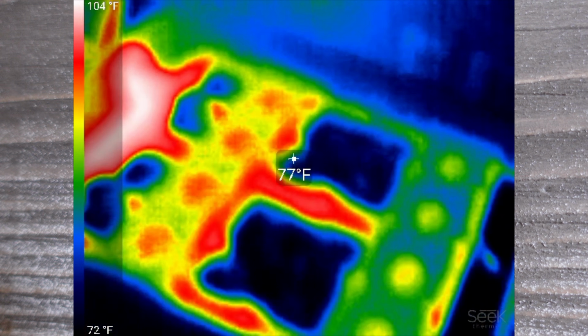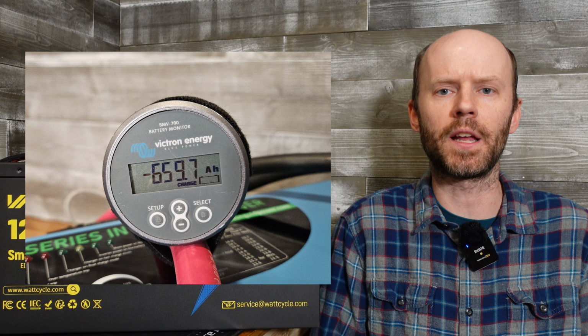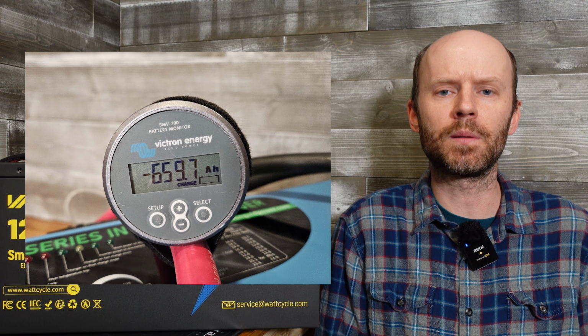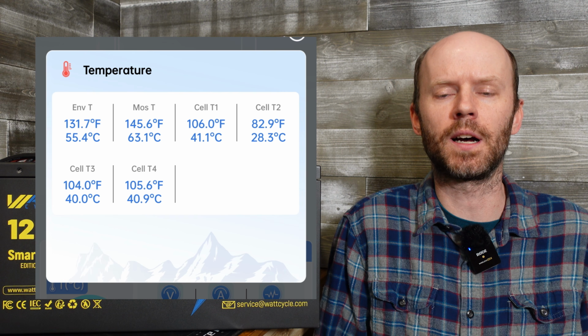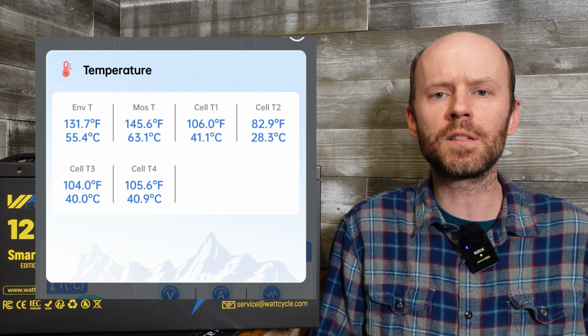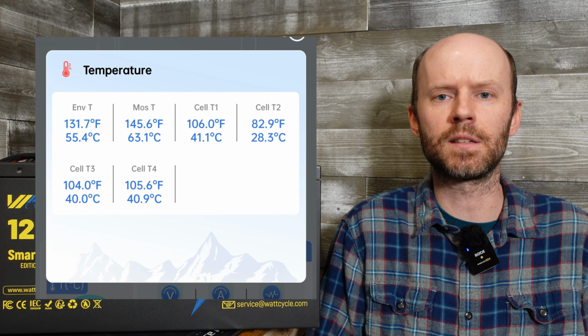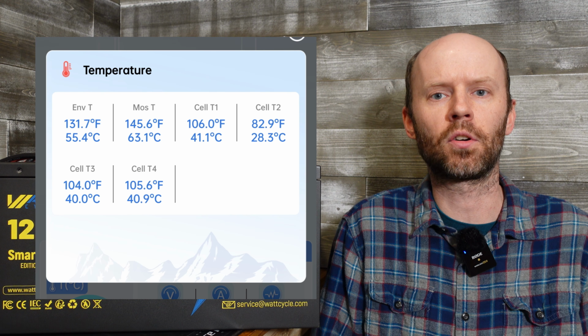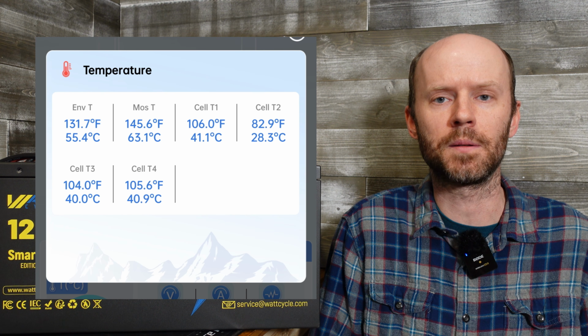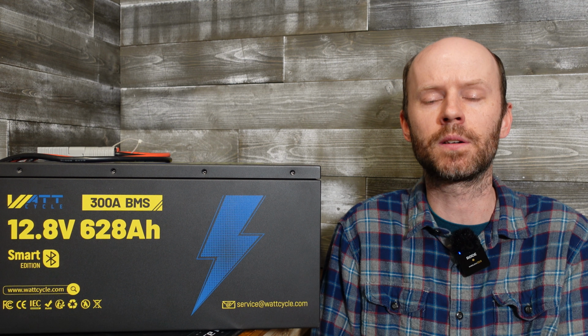Everything looks pretty good. The test completed successfully and the resulting capacity was 659 amp hours. The BMS reached temperatures of 145 degrees Fahrenheit on the MOSFET temperature sensor. It doesn't appear the shutdown is triggered by that sensor in particular, considering it is programmed for a 140 degrees Fahrenheit max discharge temperature. The battery is fully charged again, so we're going to run one more test and push it as close to 300 amps as we can. During the first test, the temperature seemed to hold steady in the 130s until near the end of the test when it started to quickly rise.